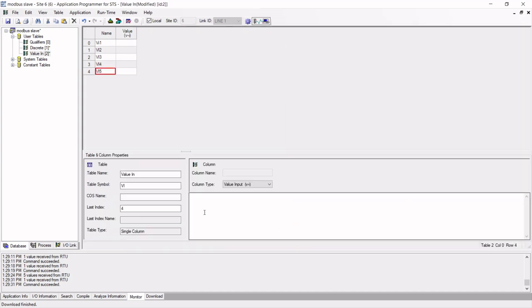Okay, so again, using the same formula. And there's our formula. So we'll just work this out. The ACE3600 data is mapped into the MODBUS database by using the formula. Okay, so here we go. Our table number is 2. 2 times 2048 plus our column is 0, so 0 times 256 plus the offset, which is 0. And that will be, in my reckoning, 4096, I hope, which I'm pretty sure it is.